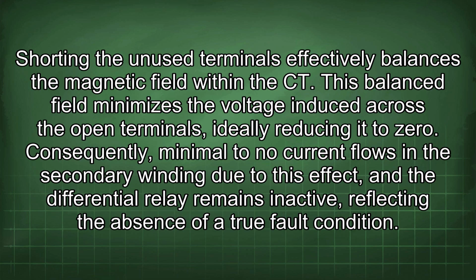Shorting the unused terminals effectively balances the magnetic field within the CT. This balanced field minimizes the voltage induced across the open terminals, ideally reducing it to zero. Consequently, minimal to no current flows in the secondary winding due to this effect, and the differential relay remains inactive, reflecting the absence of a true fault condition.